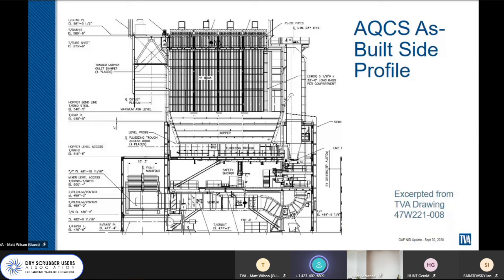And this is an automated process. Of course, it can be manual by the operators. Which modules come out of service as you come down on load and which modules go into service as you come up on load, those are operator selected, but I think the effort is to keep the operational hours across all 4 modules relatively even. So for instance, sometimes they take Delta module out, and then Charlie, and then put those back in, and a month later they may be taking out Alpha and then Bravo to try to keep everything even wear and tear. So the gas velocity is maintained by taking those modules out of service.